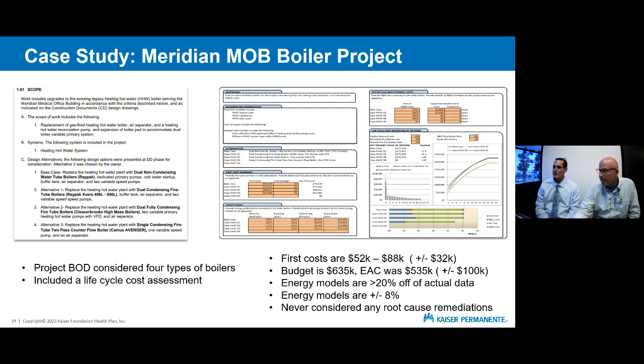So we did consider 4 different options here, but ultimately these were 4 options with just about 5% variances in efficiency, which aren't really relevant to the overall problem at the building. The building was off by 200%, 300%. So looking at 4 different boilers that are 5% off in efficiency isn't really the right tool for the job. It's probably too small on the slide, but some of these were condensing boiler options.